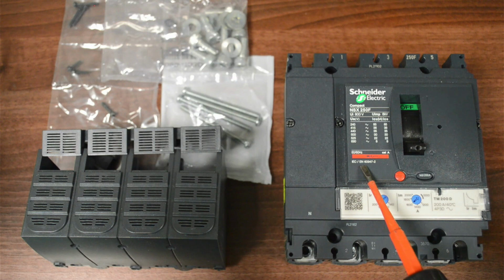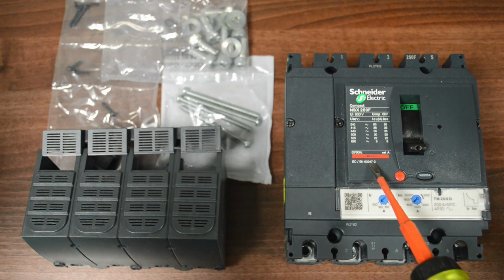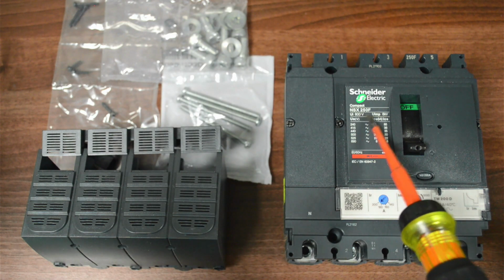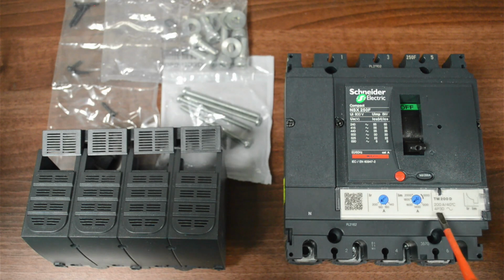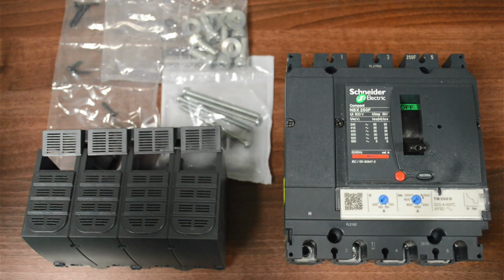You'll see here that the EN number for this is 60947-2, so that's your MCCB, and again you've got your product code on here and the actual rating and application of the device, and that's actually showing you there. I missed that out of the corner of my eye, the little graph where you've got your IR and your IM. So you've essentially got your overload, short circuit, thermal and magnetic effects of the MCCB.